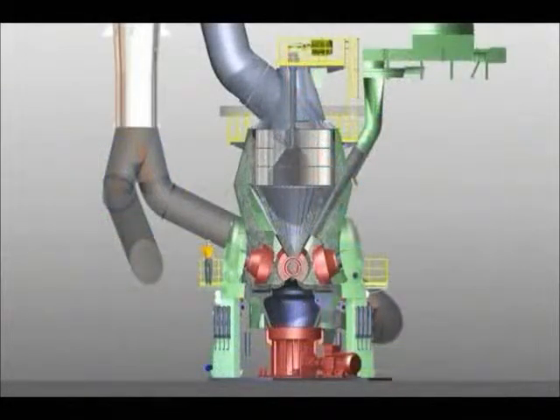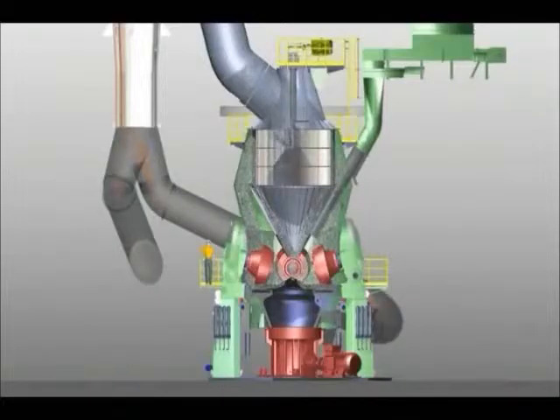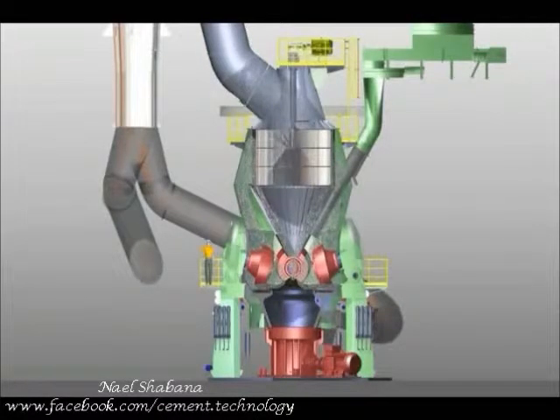The grinding plant is now performing self-inert grinding operation. Inert gases are no longer fed into the plant. For safety reasons, inert gas is only applied to the fine coal silo for the whole time that the grinding plant is running.